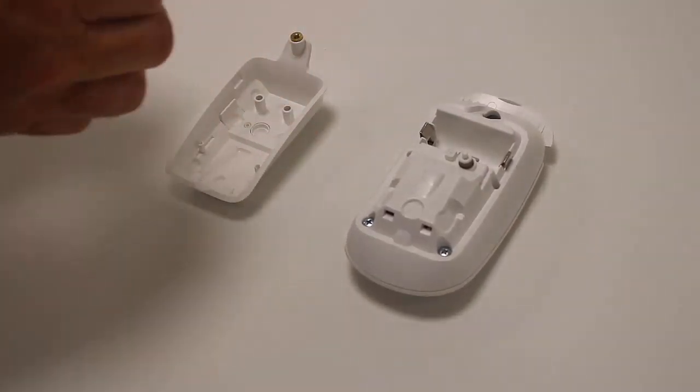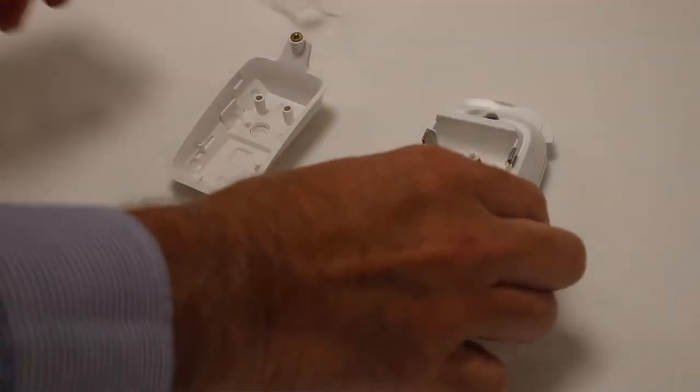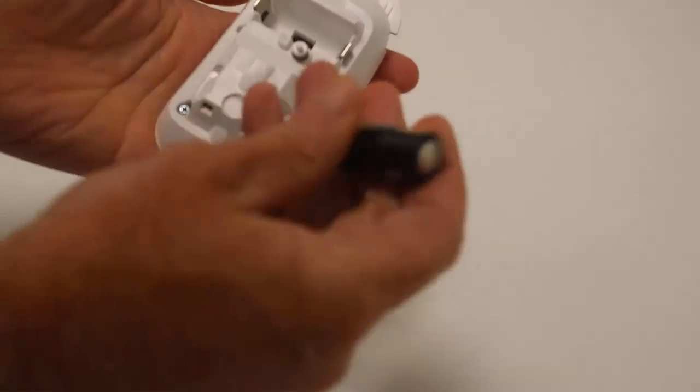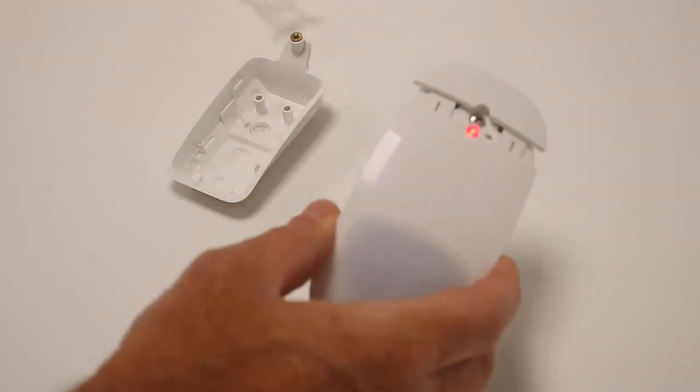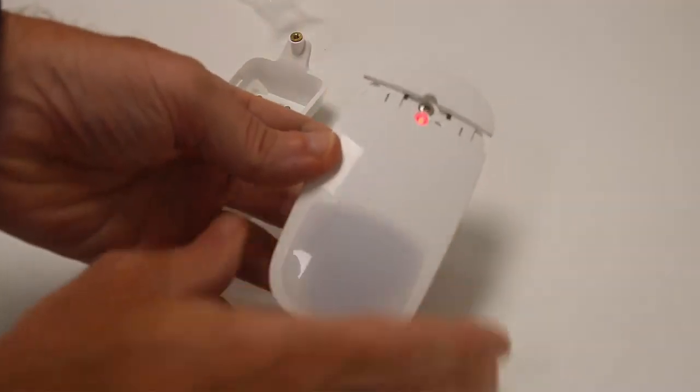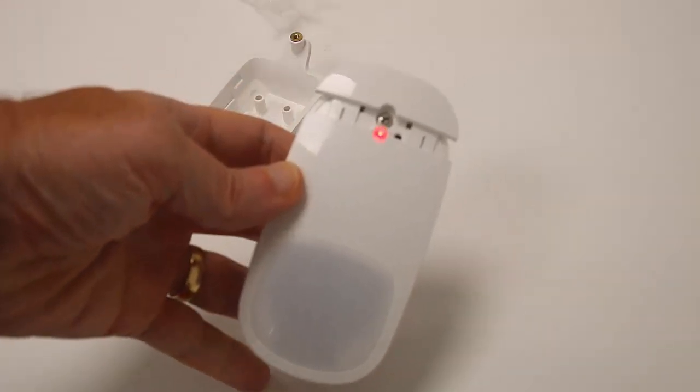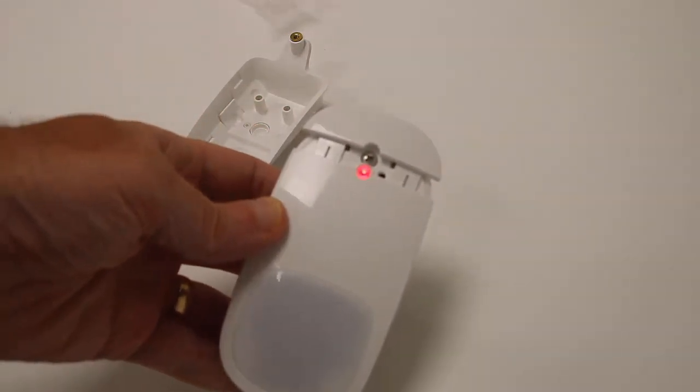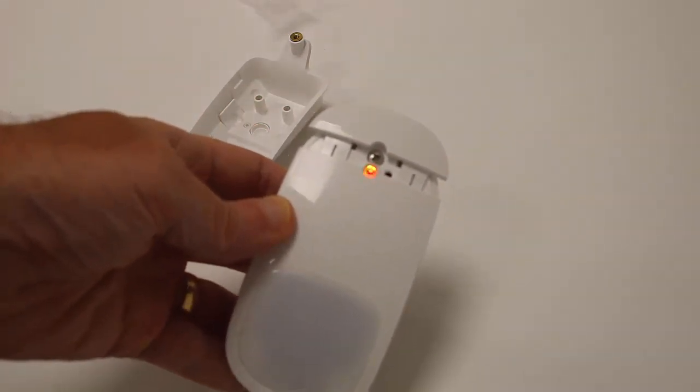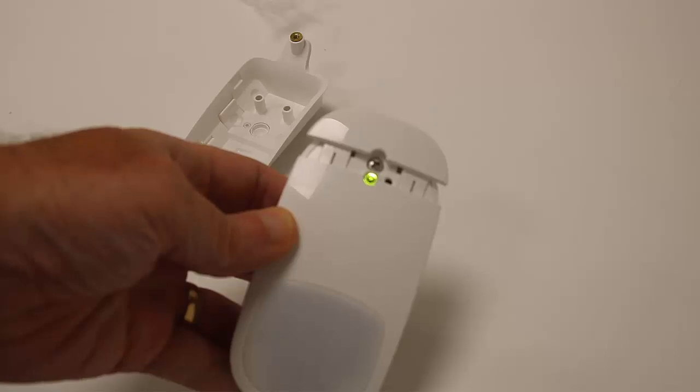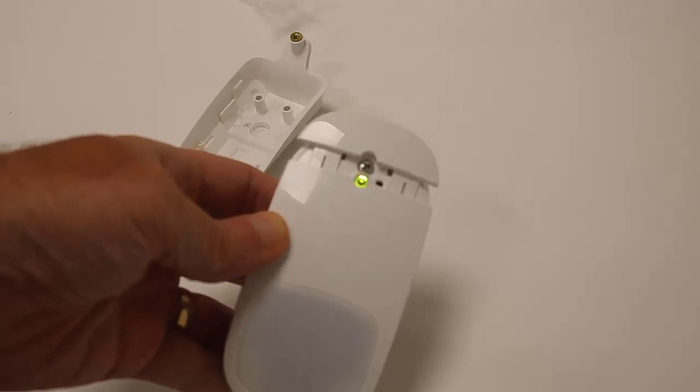We then take our device and we place the battery into the device. When we put the battery initially into it, it puts the device into enroll transmission mode. In this case the WPIR, the wireless PIR detector, goes into a diagnostic mode first of all. This takes about 20 seconds.